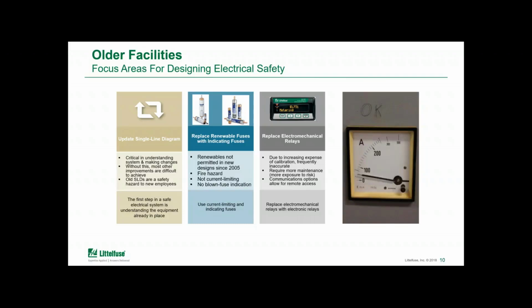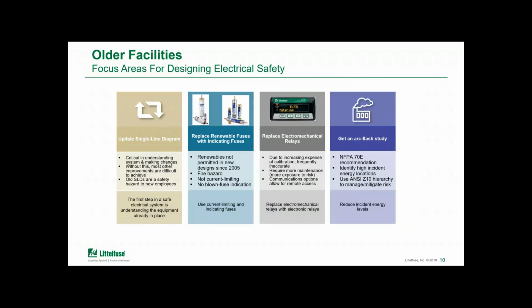Now, this is a photo here that a colleague of mine took when he visited a site, and in this case, the operator was supposed to take an action if the ground fault current exceeded the pen mark on the meter. And despite that the pen mark is not exactly easy to read, this is really not going to qualify as being a great method for doing that.